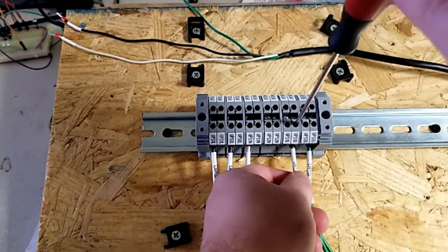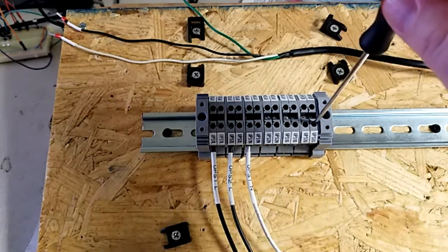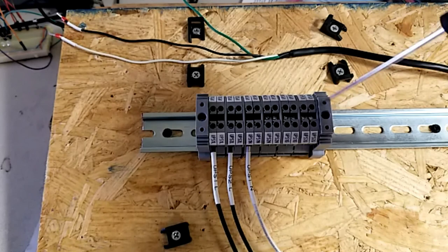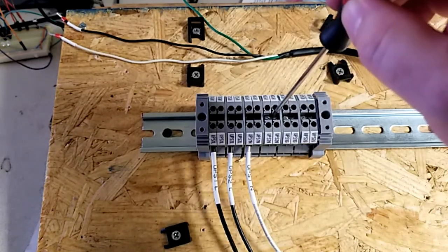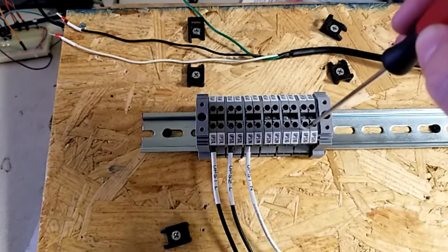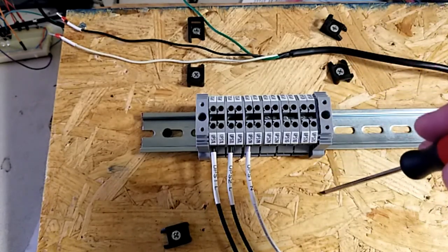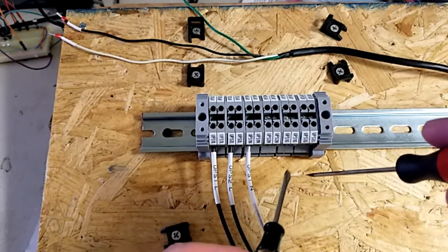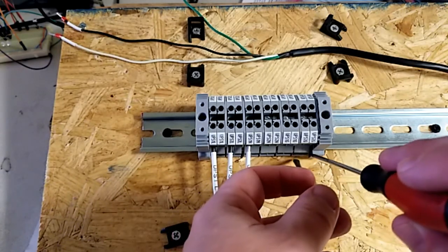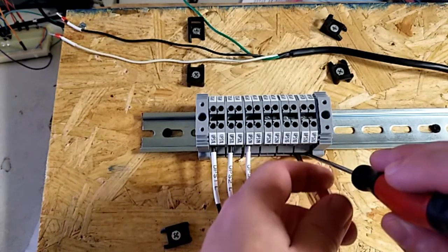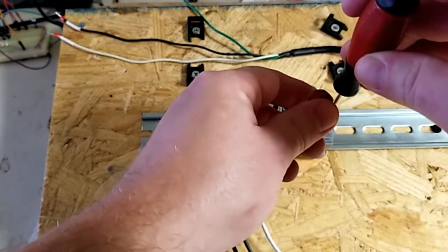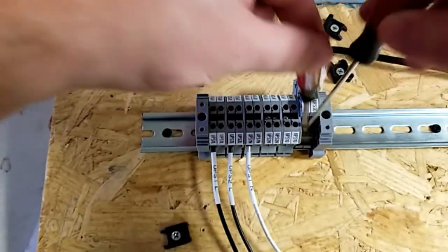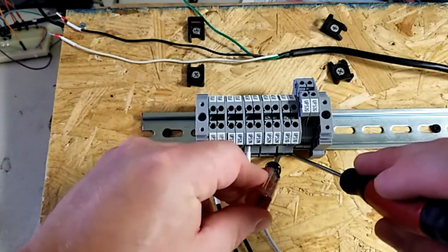So we're going to remove this one, we're going to remove this one. So we're going to replace all six of these terminals. So each of these is jumpered together, so they're in pairs of two. So rather than removing the jumpers, we can remove the pairs together. So if we take two small screwdrivers, we can go into the clips on the bottom of each of these terminals, and we just pry slightly and you'll see the terminal pops up. I'll try and do another angle so my hands don't get in the way.